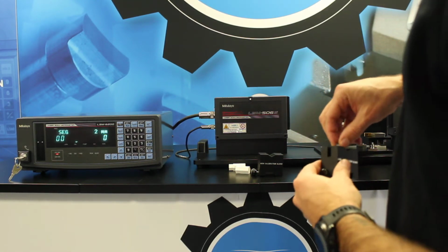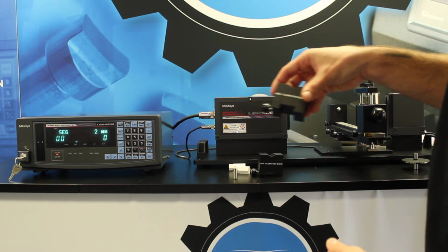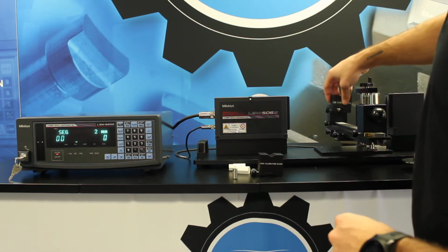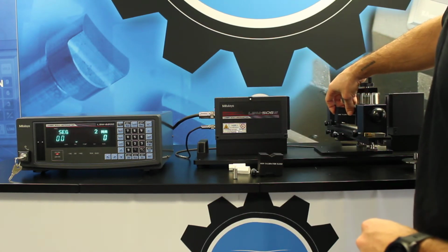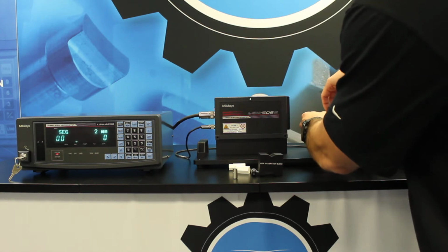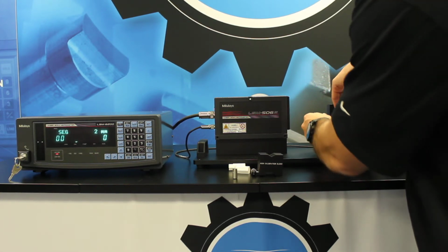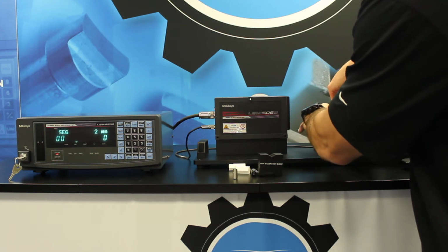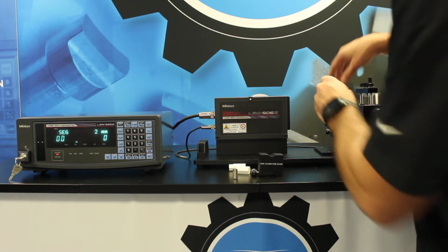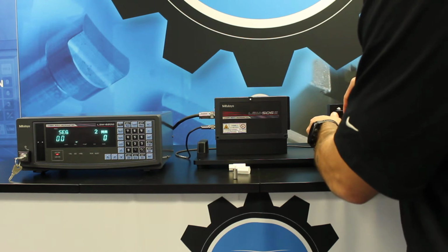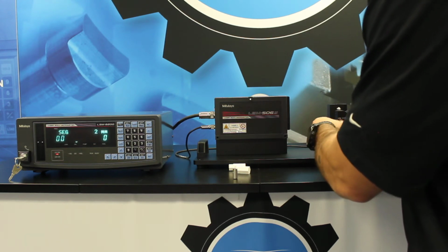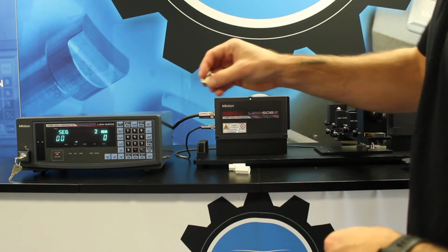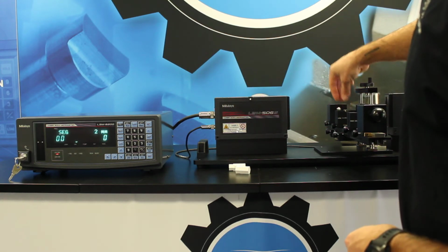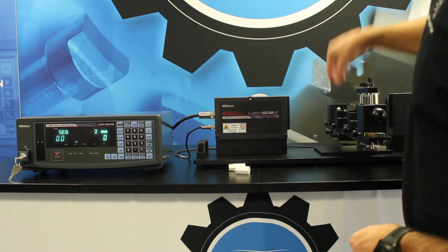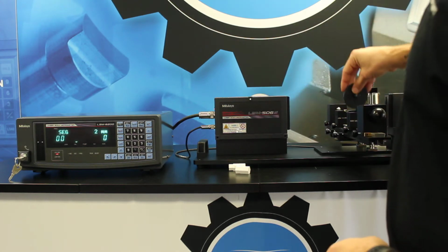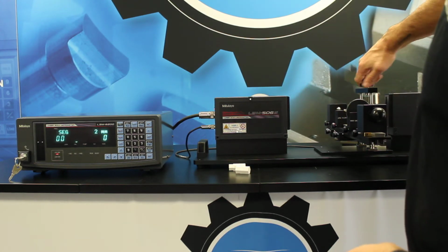I'm going to carefully install my low calibration block first. It does not matter if you install the low calibration or the high calibration block first, or where you put them along the rail. What's important is that when they're on the rail, you lock them in tight with the thumb screws. So I'll install each block. I'm going to install the low calibration artifact into the low calibration block, and the high calibration artifact into the high calibration block.